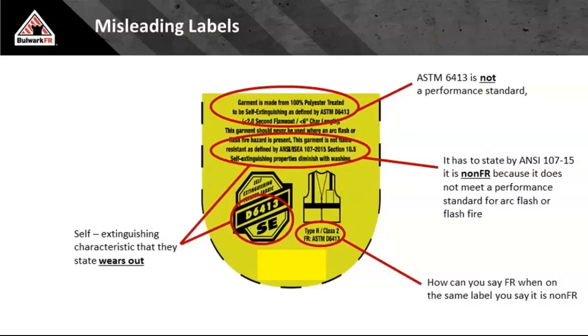Why are we adamant about this? This is what I see in the field. I see things like this. I see claims that this particular high-vis garment is tested to 6413, claiming that it has self-extinguishing properties, which are alluding to that in some way, shape, or form, it has something that's kind of flame-resistant. Self-extinguishing has nothing to do with flame resistancy when it comes to arc flash and flash fire. Secondly, it says on the same label of the same garment that self-extinguishing properties diminish with washing. What? So if you're taking something like this and thinking you have some FR, you could be dead wrong.